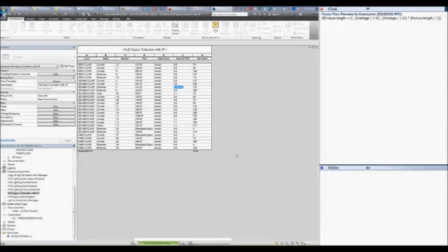For this, we're under LEED 2009, so it's ASHRAE 90.1, 2007 that sets the allowed watts per square foot we're operating under, since they don't have to do Title 24 if they don't want to. Again, it's live. For example, for this corridor, if corridors are only allowed 0.4 watts per square foot, you can just go in there and change it.